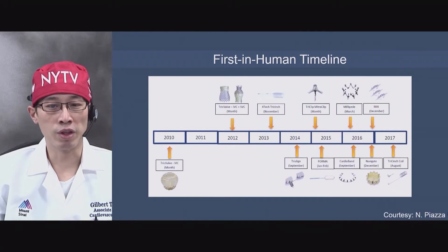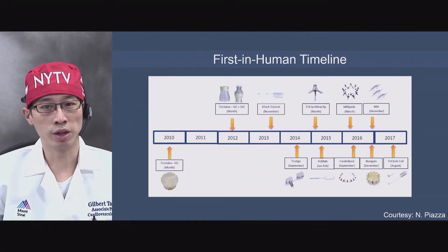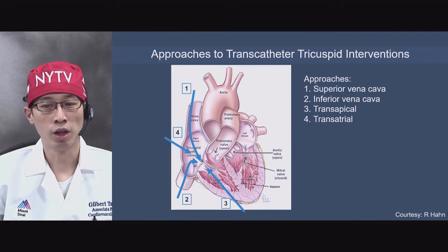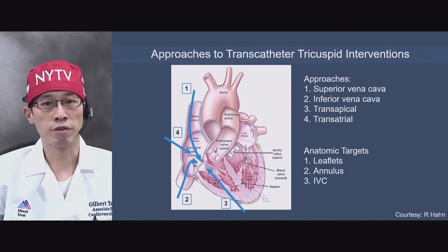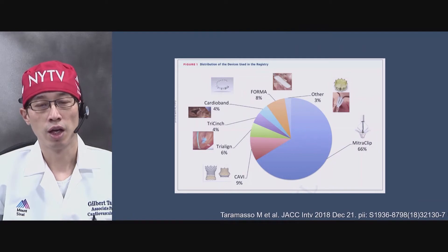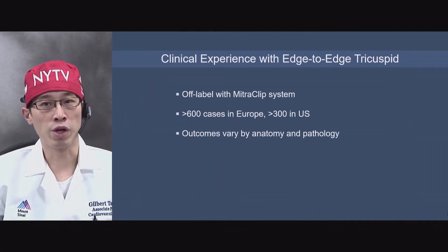A number of devices have first-in-human experience, beginning from a replacement device in 2010 to more recently 2017 with some repair devices. They typically approach from a number of access routes — SVC, IVC, transapical, transatrial — and they target three anatomies: either the leaflets, the tricuspid annulus, or the inferior vena cava. In a multicenter international registry on patients who underwent transcatheter tricuspid therapy, the majority underwent MitraClip to repair the tricuspid valve, as it was the only commercially available device at the time. For the edge-to-edge tricuspid repair, most were done off-label — over 600 cases in Europe and over 300 in the United States — and outcomes vary by anatomy and pathology.